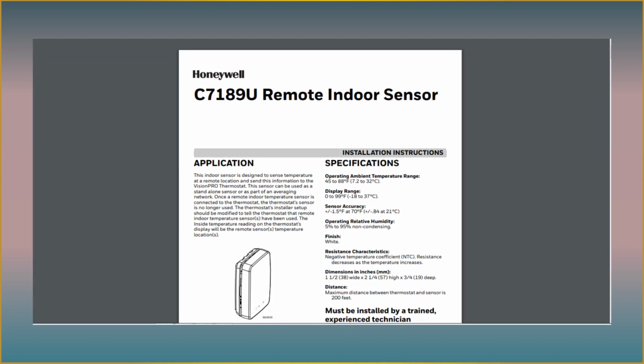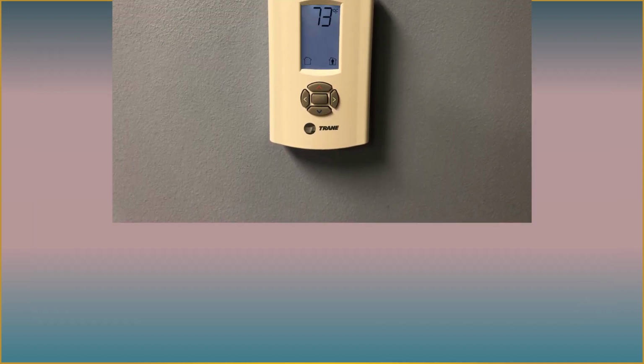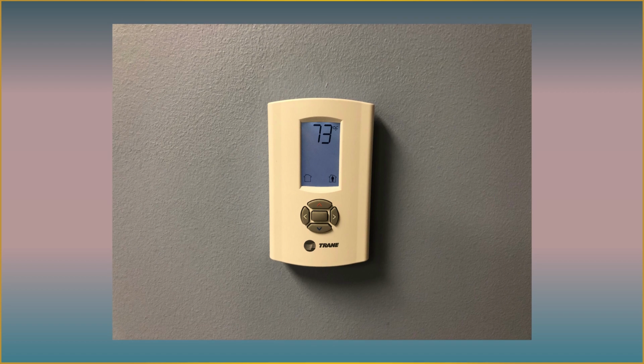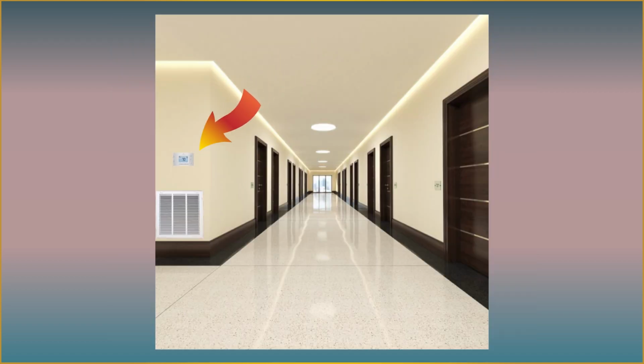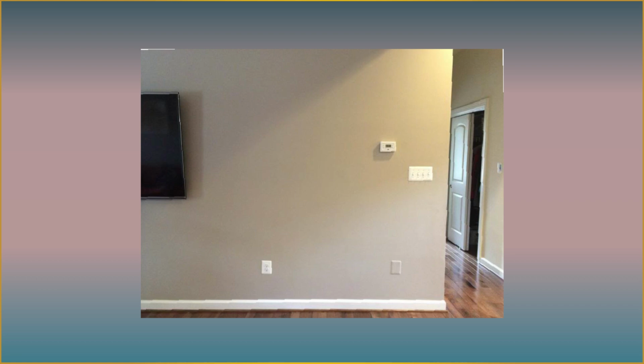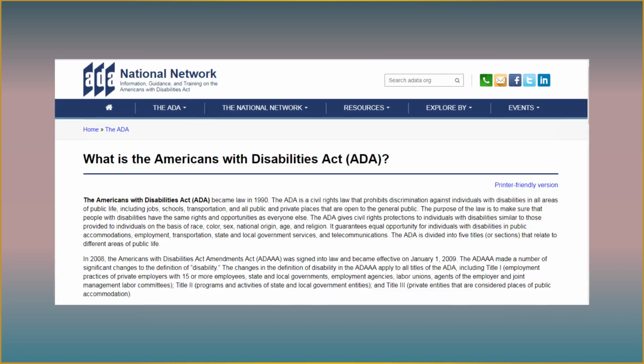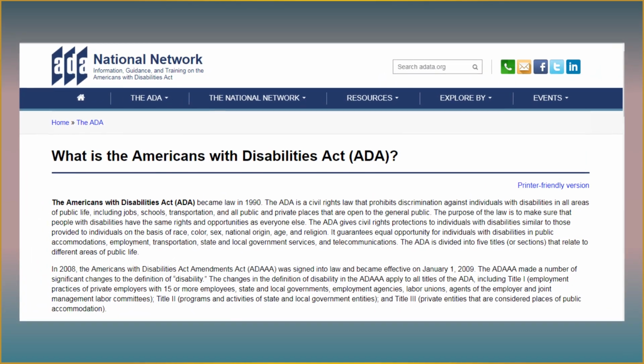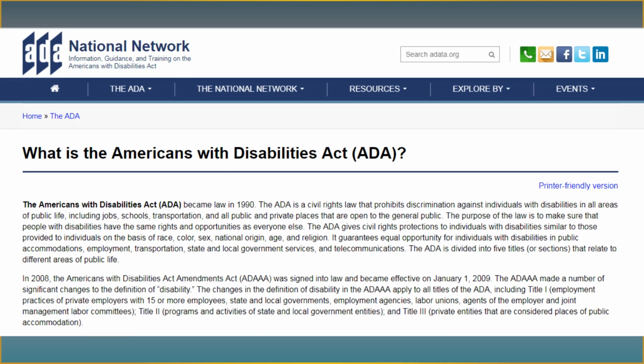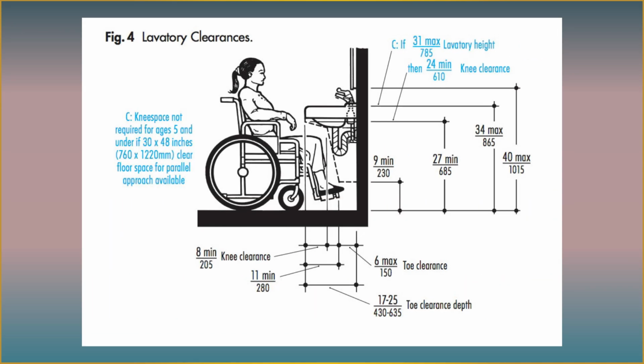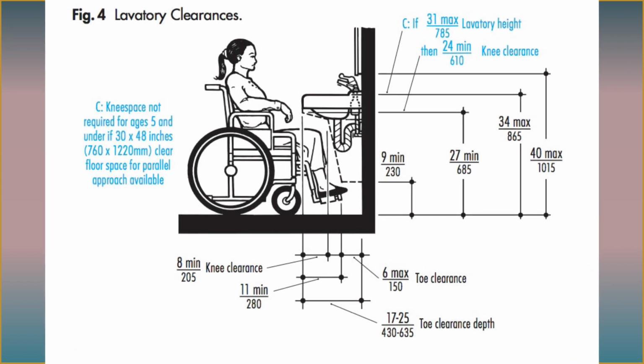With most HVAC systems, the thermostat is located on a wall or pillar in an area near the return grill for the unit that it's connected to. In a regular built home, the thermostat should be mounted at 60 inches to center or 152 centimeters AFF, which means above finished floor, and 48 inches or 121 centimeters centered for ADA. ADA is the Americans with Disabilities Act, which is for buildings like schools, government buildings, and hospitals.